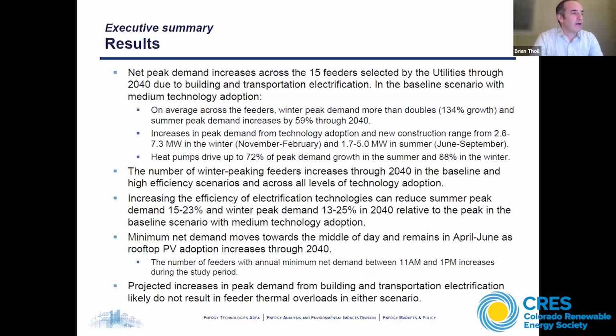But what we were looking at, across these 15 different feeders that were selected, the data input was 2022, and from 2022 to 2040, in this baseline scenario, we could foresee winter peak demand growing up to 134% on individual feeders, and a corresponding growth in summer peak demand by about 59% by 2040. Largely, as you'll see later in this slide and in other areas, heat pumps are the primary driver for that growth. We'll do a little comparison to other technologies as we go here.